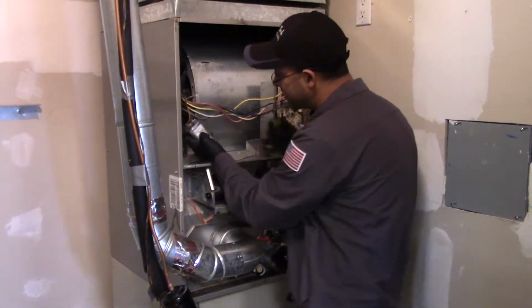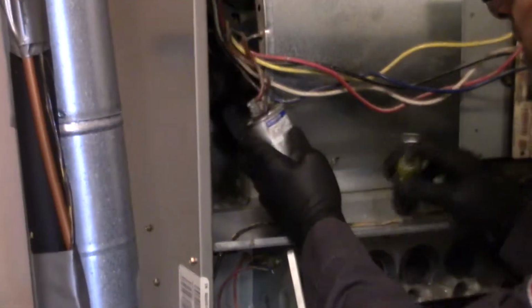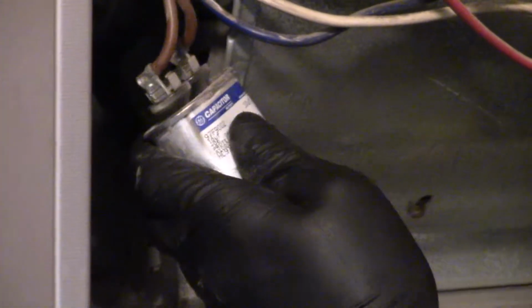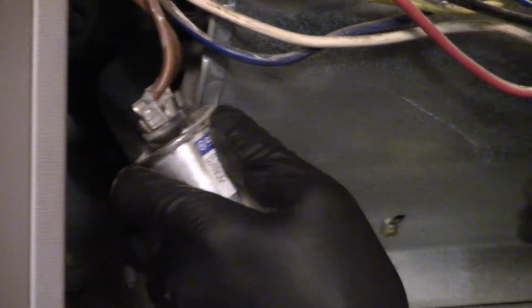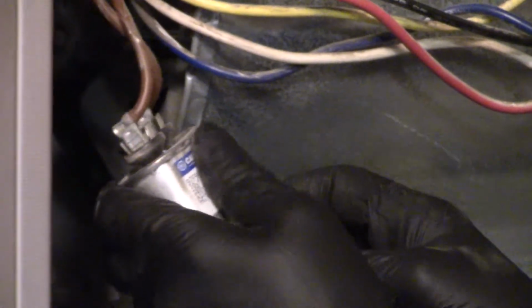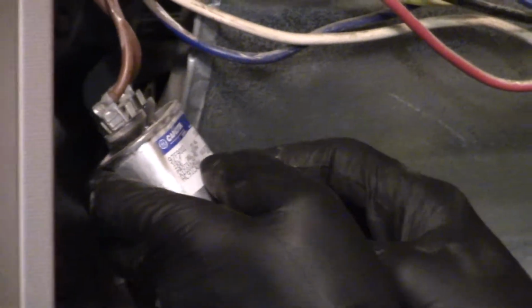So when I'm looking at this, I've got to really make sure that somebody didn't come in here and just throw on a capacitor. Maybe if I ask the customer to find out the history, or if anybody's worked on it, I can find out if another company was in here and put the wrong capacitor. So maybe that's why the motor's not working or it's burned out.